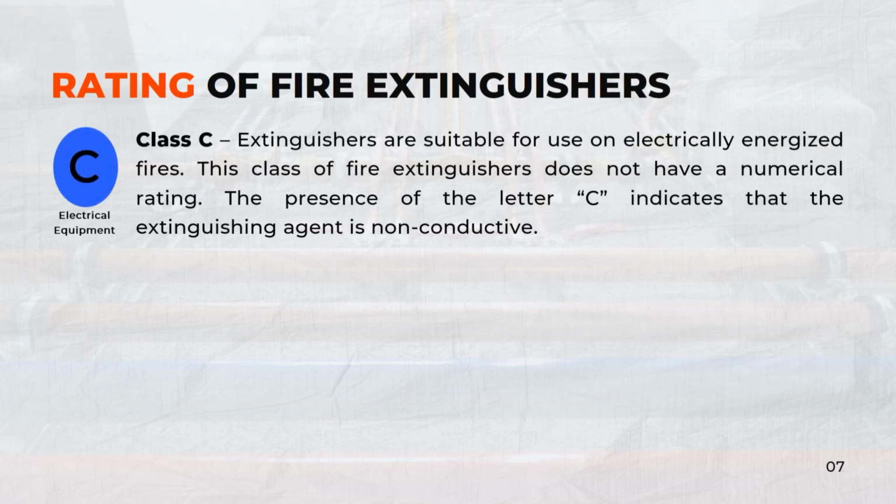Class C extinguishers are suitable for use on electrically energized fires. This class of fire extinguishers does not have a numerical rating. The presence of the letter C indicates that the extinguishing agent is non-conductive.